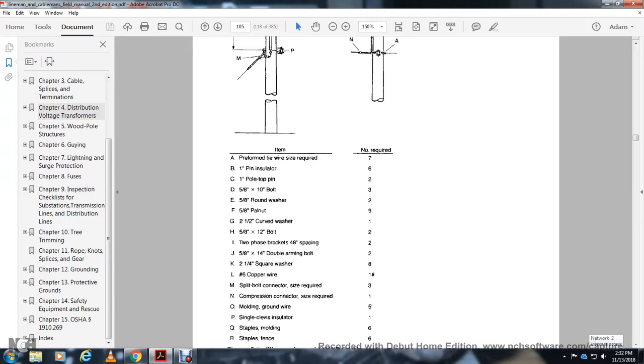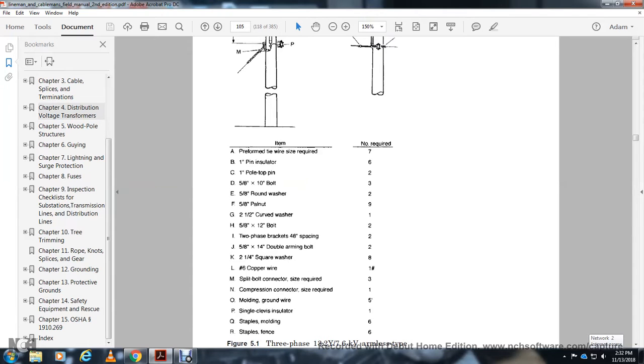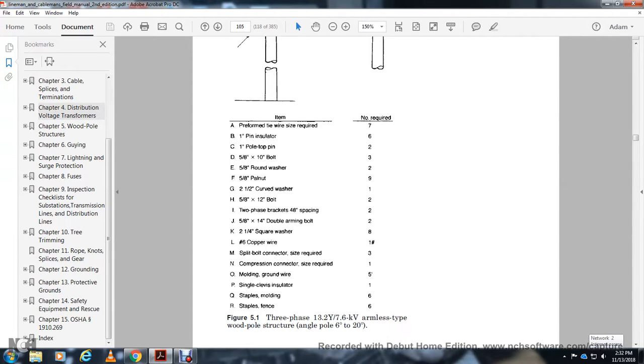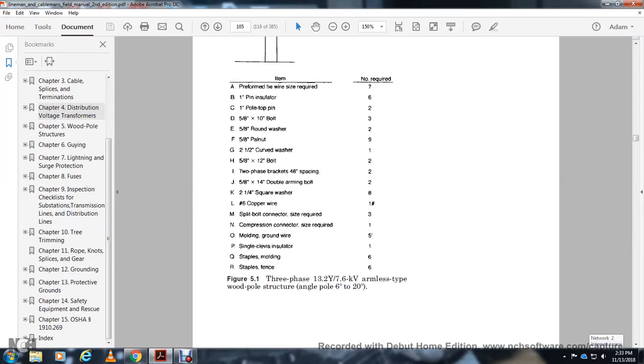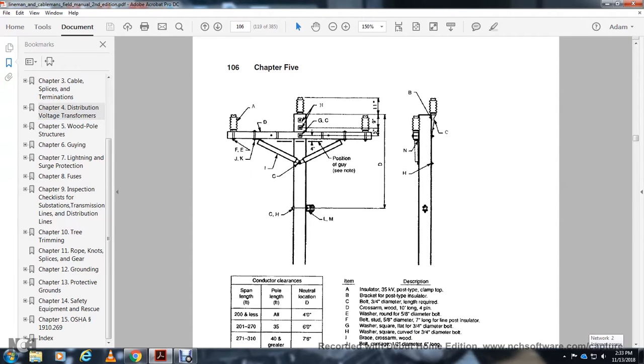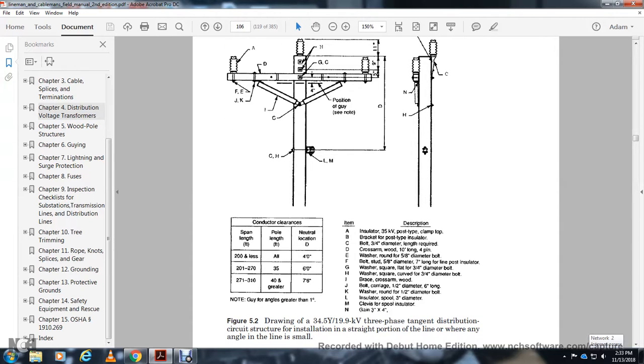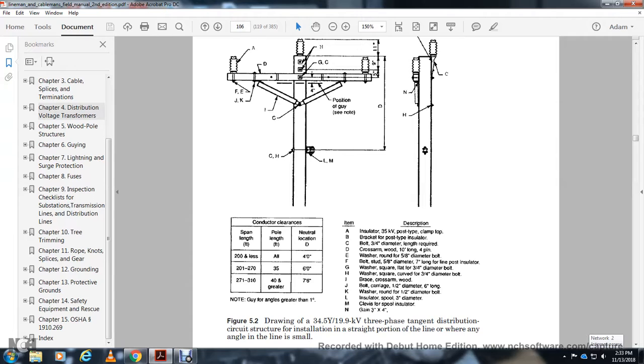Figure 5.1: Three-phase 13.2 kV Y wire connection, 7.6 kV armless type wood pole structure for angle poles 6 to 20 degrees. Shows components A through M. Conductor clearance, span length: 200 feet or less, 201 to 270, 271 to 310 feet, pole length, and neutral location.